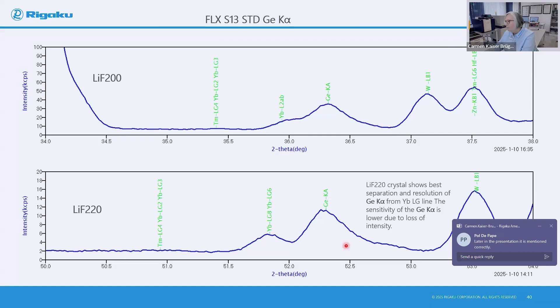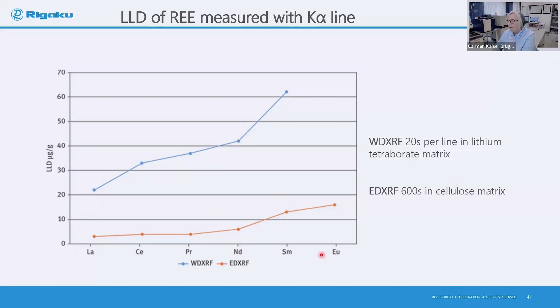So here you can see an example of the comparison of WD and energy dispersive XRF limits of detection. For WDXRF, the measurements were done with 20 seconds per line using a lithium tetraborate matrix, and we compare it to 600 seconds with energy dispersive in a cellulose matrix. So from lanthanum to europium.